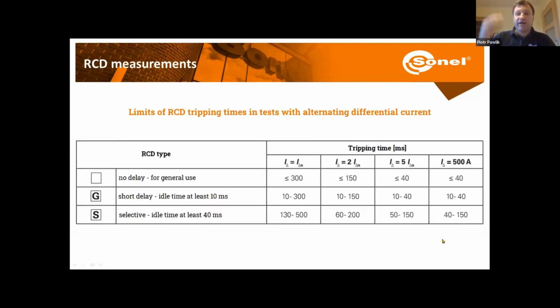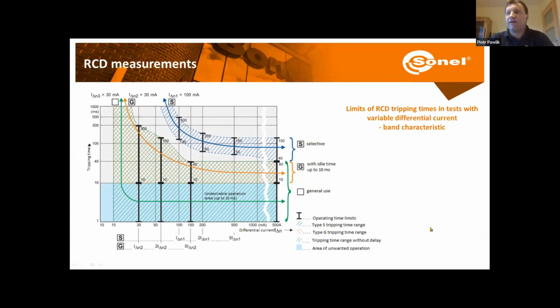Now we can also divide RCDs depending on their triggering time. So the general ones with no delay, short delay ones with idle time of at least 10 milliseconds, and selective ones with idle time of at least 40 milliseconds. So once we look at the characteristics of this RCD, here we can see the tripping time, and here we can see the differential current.